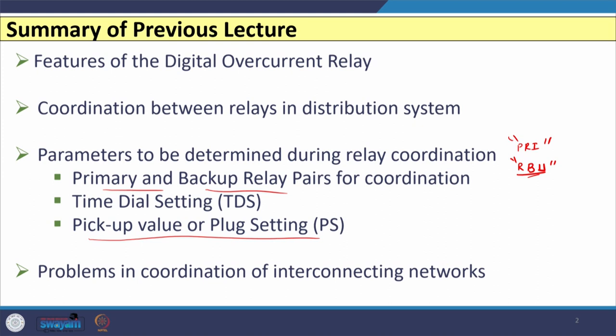After determining these three settings, manual calculation is not possible. The reason is that the network we consider may be a radial distribution network fed from multiple ends, a multi-source system, or a ring main system. When such different distribution network structures exist and the number of relays and distribution feeders is large, we have to use an algorithm and write code in some language, whose output will give these three settings.